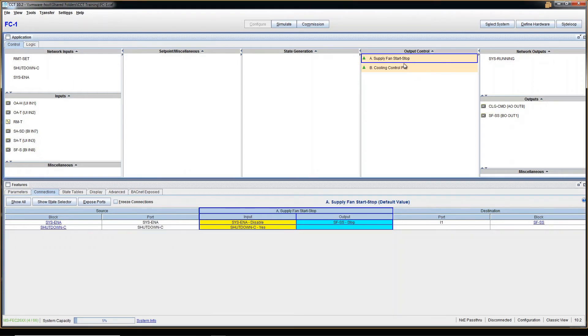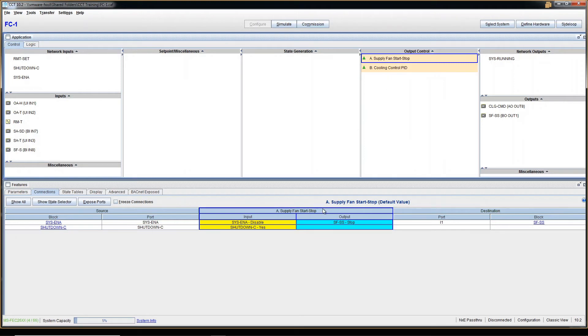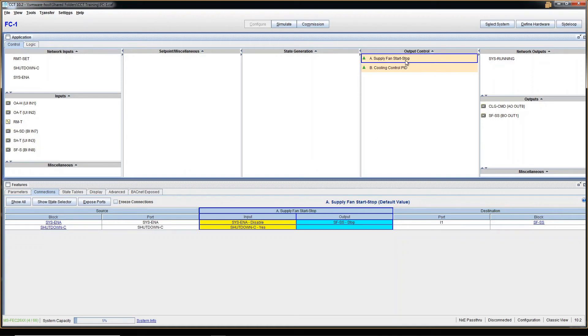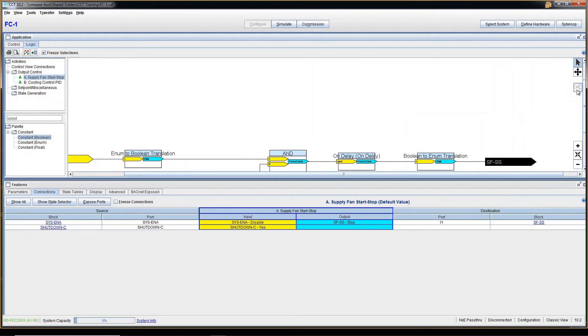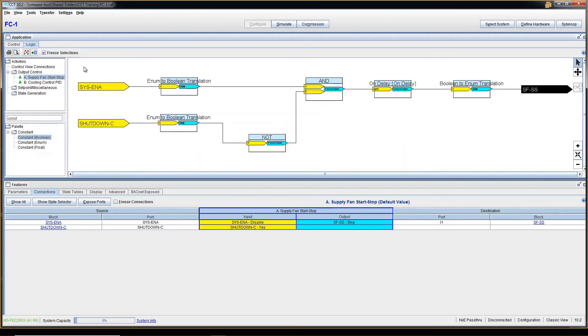The last thing I want to talk about is the inputs and outputs of the programming blocks. As I click on a block, the bottom part updates under the connections tab. For the Supply Fan Start/Stop programming block, you can see it has two inputs in yellow and one output in light blue. Same thing with Cooling. If I right-click on the Supply Fan Start/Stop program block and view logic, we can see two inputs and one output — the inputs and output are Enum types.